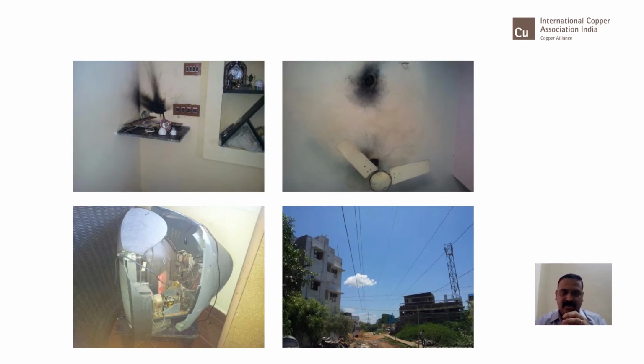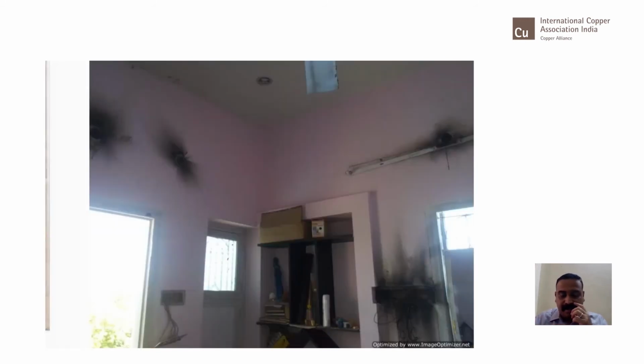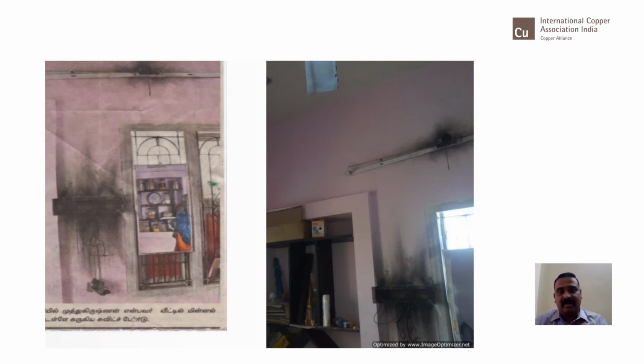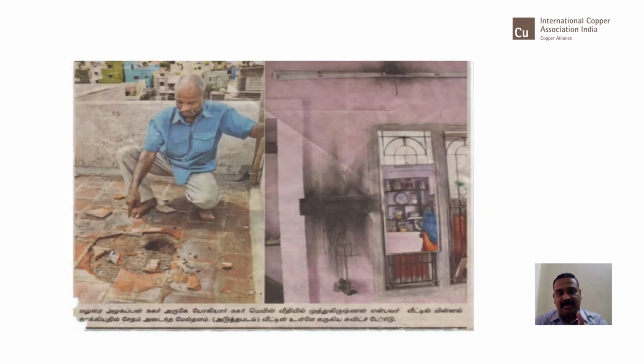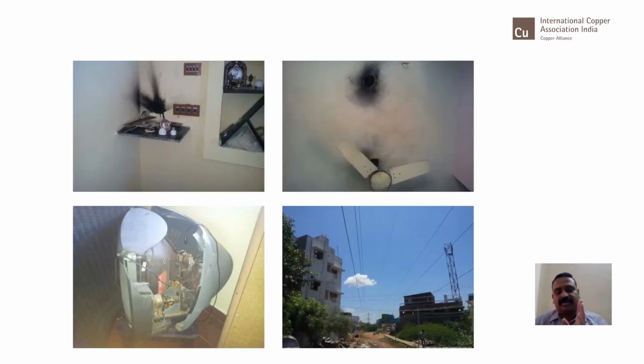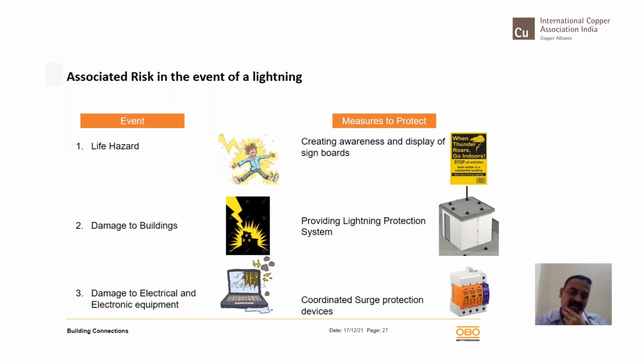So now if the client goes with an external lightning protection alone for the building, this failure would have still continued because the source of lightning entering the building was entirely different. That is why the standard defines 4 sources of lightning strikes inside. I'll just explain when it comes to the next slides.